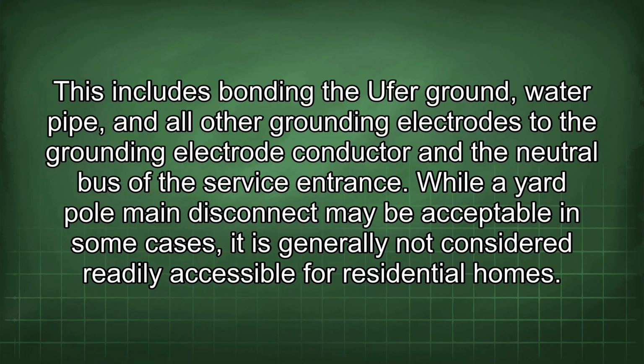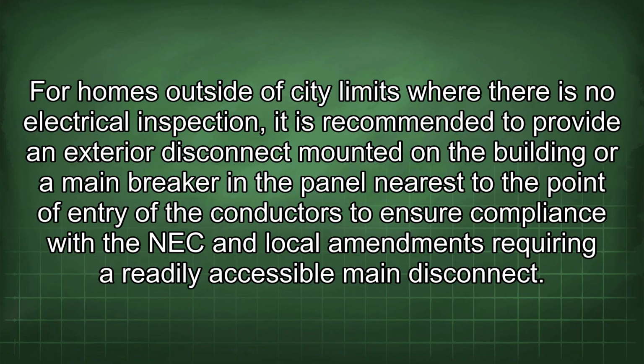While a yard pole main disconnect may be acceptable in some cases, it is generally not considered readily accessible for residential homes. For homes outside of city limits where there is no electrical inspection, it is recommended to provide an exterior disconnect mounted on the building, or a main breaker in the panel nearest to the point of entry of the conductors, to ensure compliance with the NEC and local amendments requiring a readily accessible main disconnect.